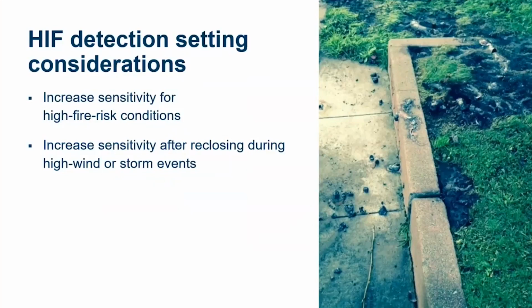We recently published a paper with PPL on their experience applying high impedance fault detection. One of the things they mentioned in the paper, about how they use this HIF mode, is that for many of their down conductor events, especially during storms, they would first see an initial fault that they would trip for using their traditional fast curves. And then when they reclosed, they would reclose into a high impedance fault and never trip.